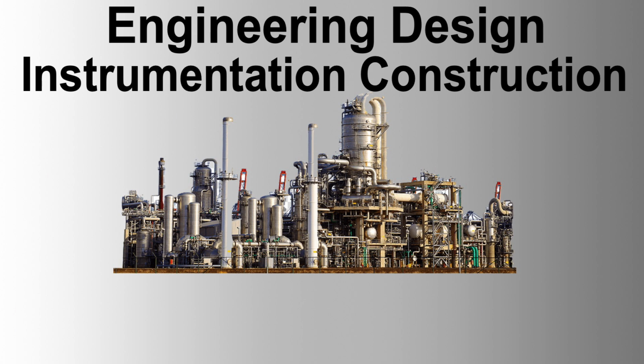Testing procedures. Each instrument loop shall be checked for proper wiring and termination. This includes verifying that the wiring matches the project drawings and that all connections are secure. Signal continuity shall be tested from the field device to the control system. This includes checking for any open circuits, shorts, or incorrect wiring.